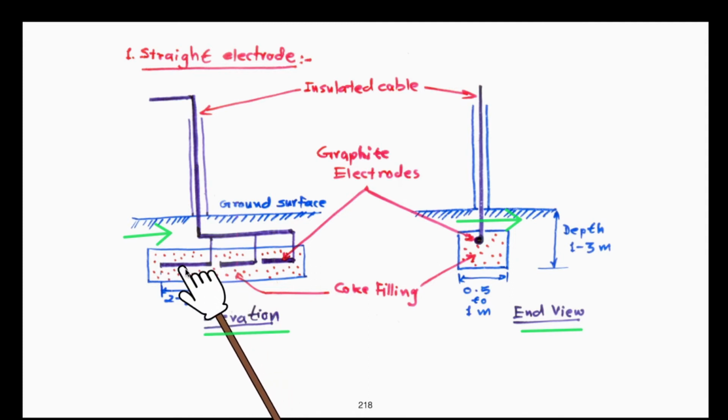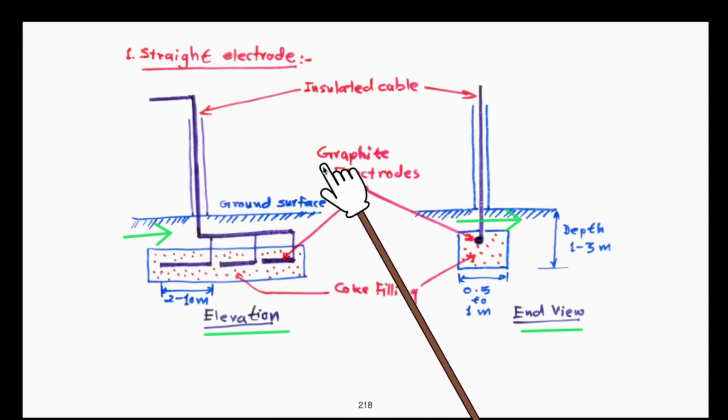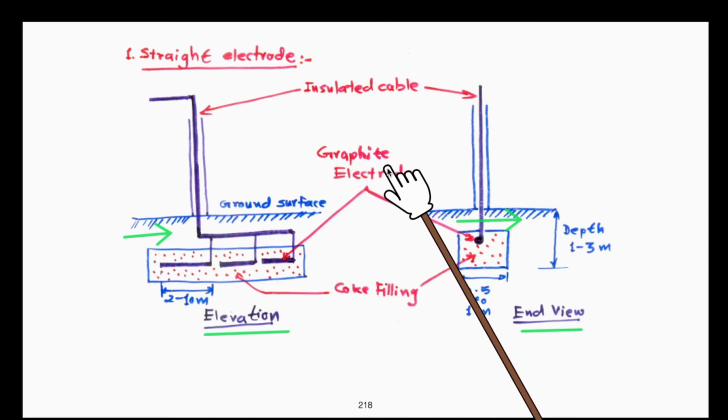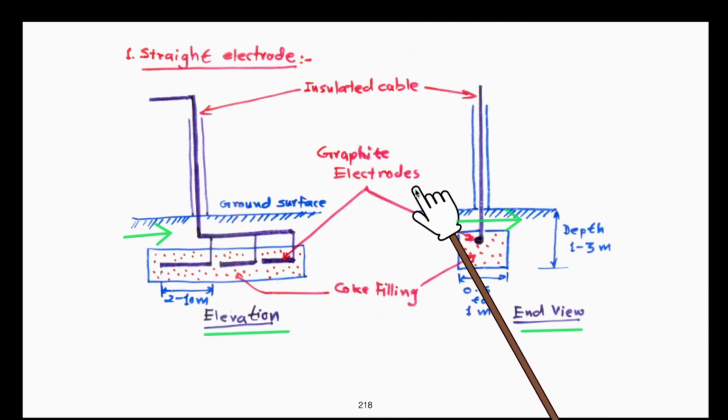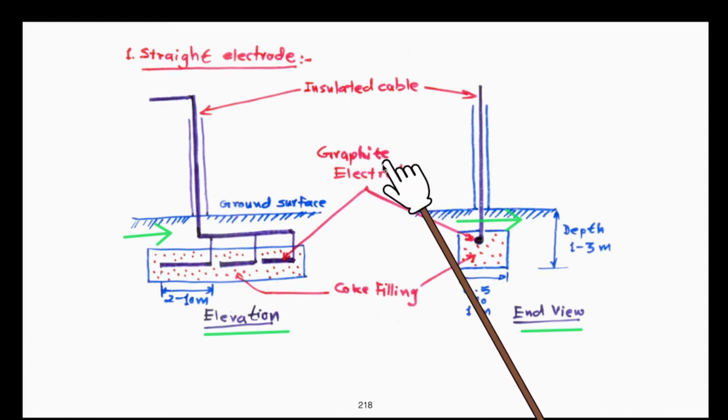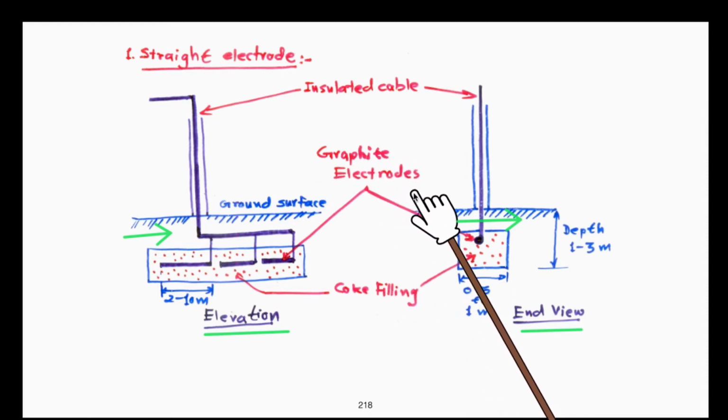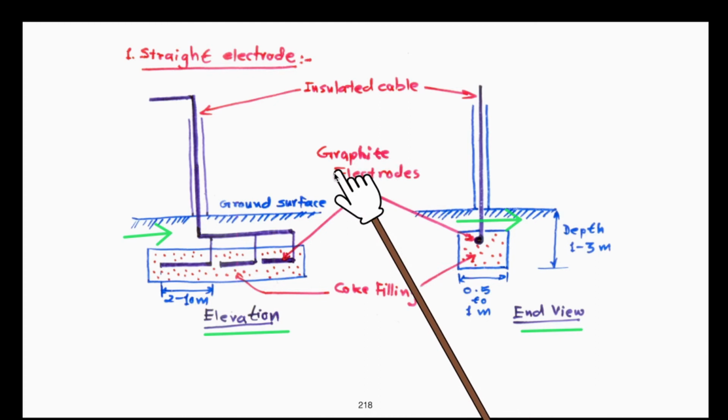So it requires frequent replacement of the fresh array of electrode elements, maybe after 6 months or 1 year, depending upon the size and dimensions of these electrodes. But later on, with the development, it was realized that graphite has much better electrolytic properties, and it opposes corrosion and consumption of electrode material with a flow of DC current.